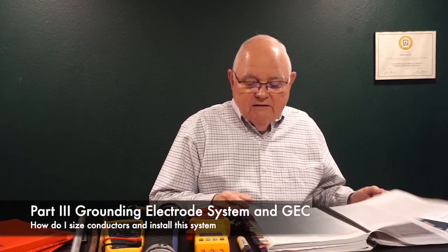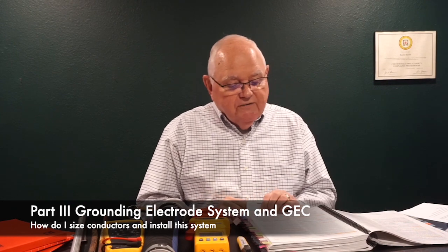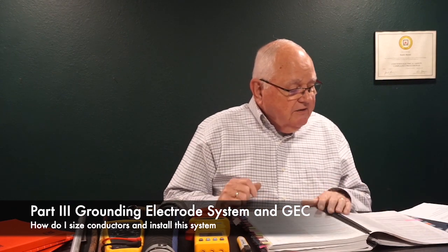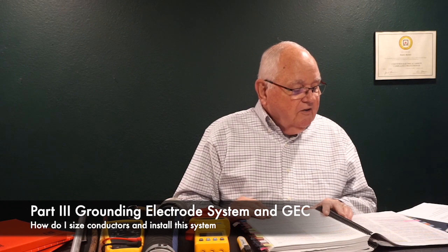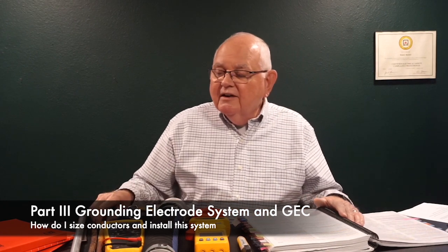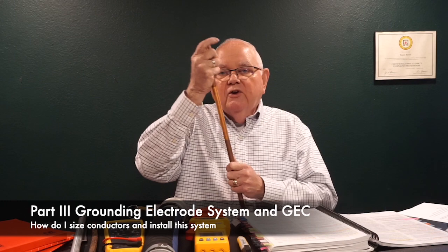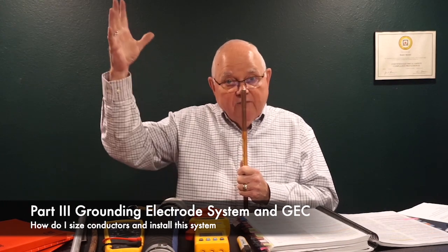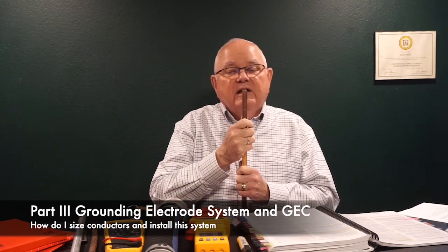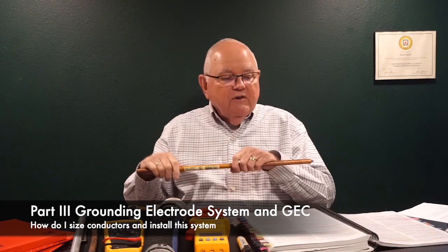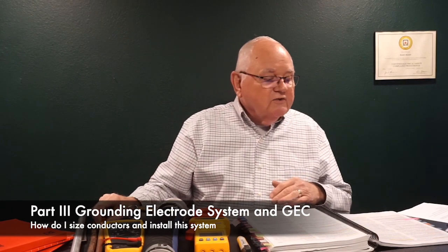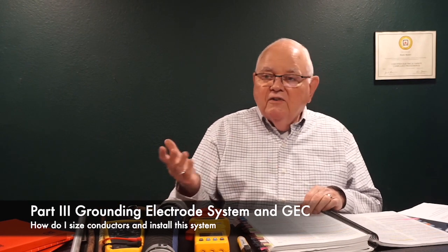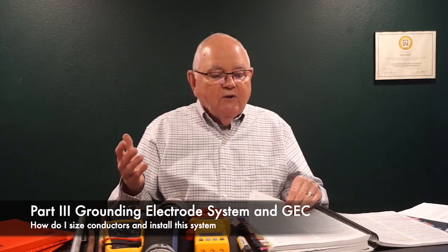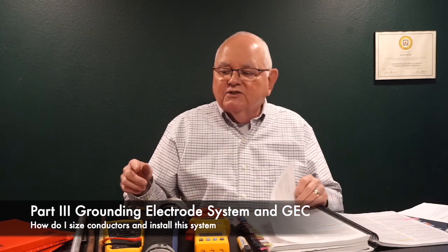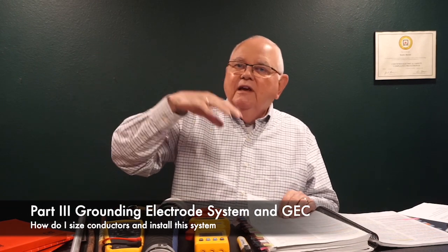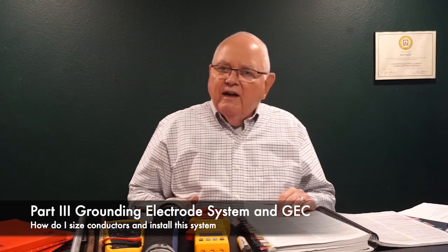Part three of Article 250 now gets into the grounding electrode system and the grounding electrode conductor. So the grounding electrode system, what am I going to put underneath the earth in order to ground my distribution system? That's my grounding electrode system. So if I have a question of what type of grounding electrodes can I use? How do I install these grounding electrodes and so forth? How do I size these grounding electrode conductors that connect from my distribution system down to my grounding electrode system? That's all found in part three then.